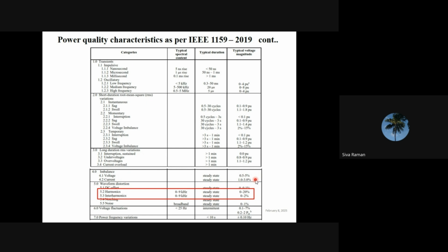And importantly, our topic comes under waveform distortion. So here there are two parameters, harmonics and interharmonics. So that is our topic. So harmonics are integral multiples of the fundamental frequency of 50 hertz or 60 hertz. And interharmonics are the components which are not integral multiples of 50 hertz or 60 hertz. And voltage fluctuation and power frequency variation, I am not going to touch on those.